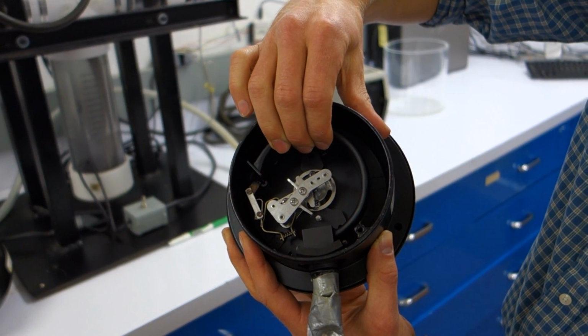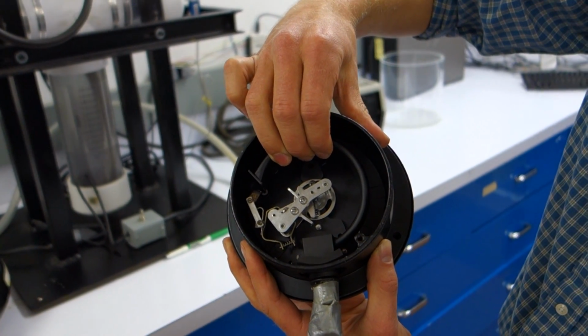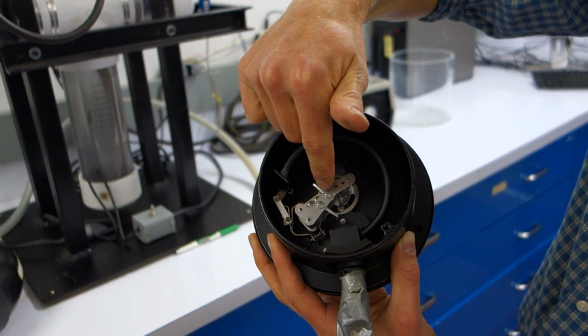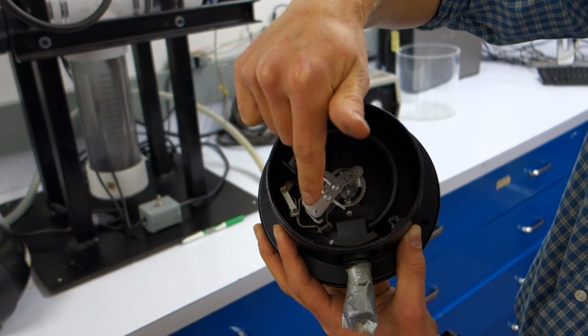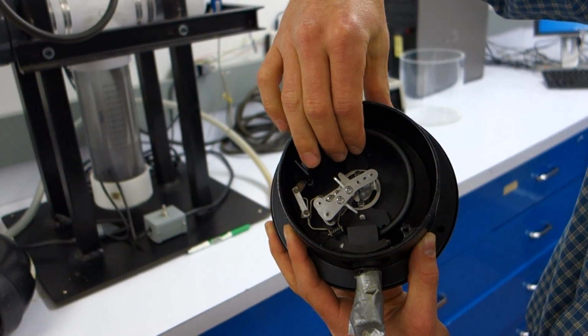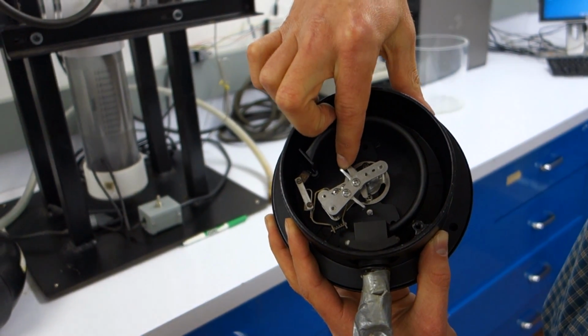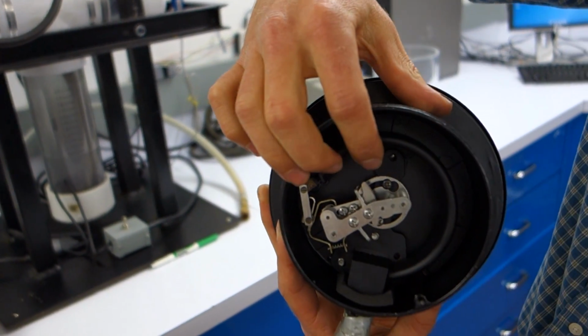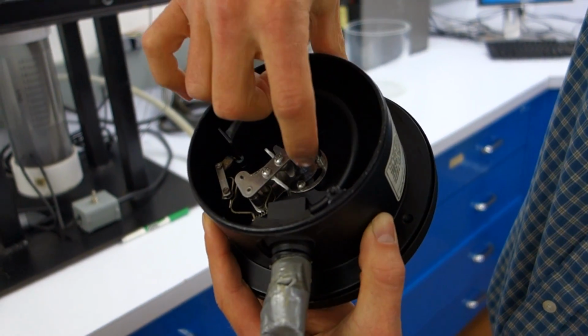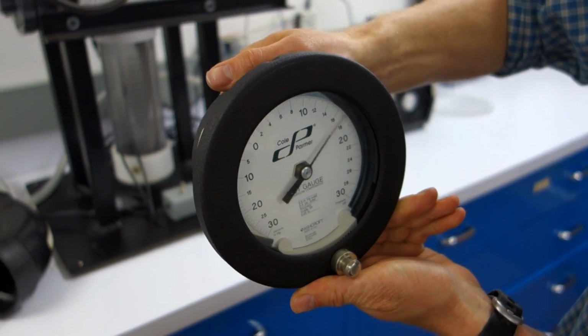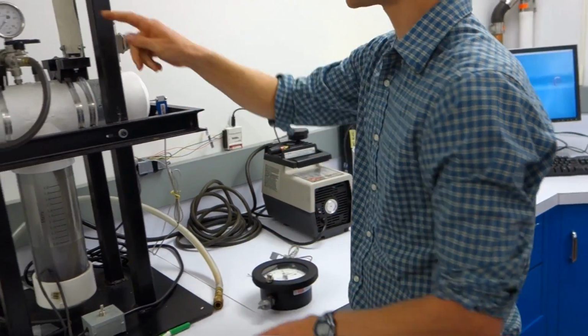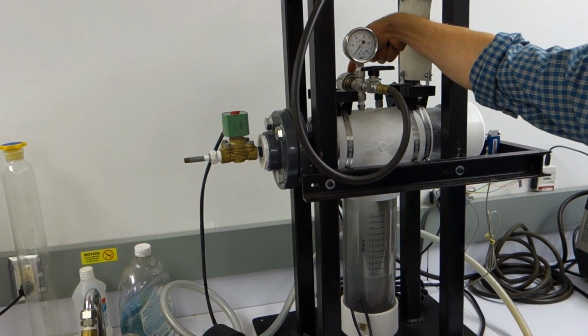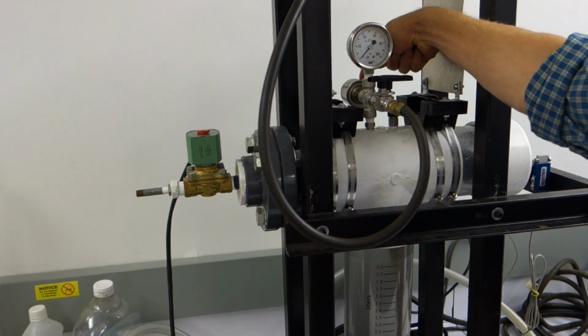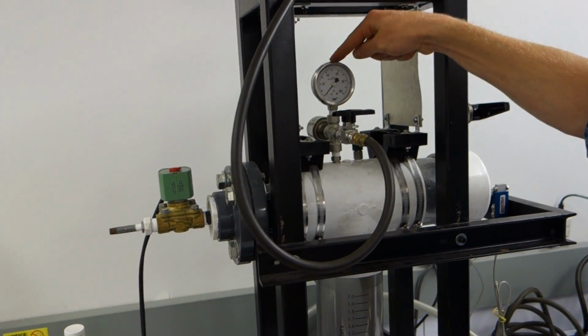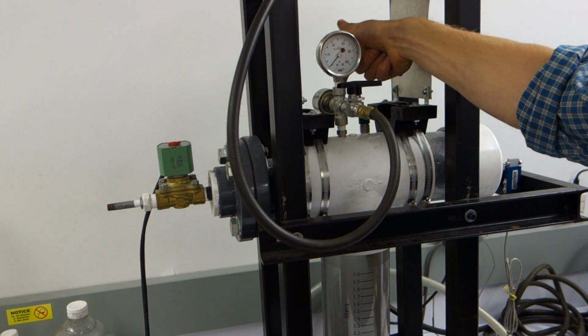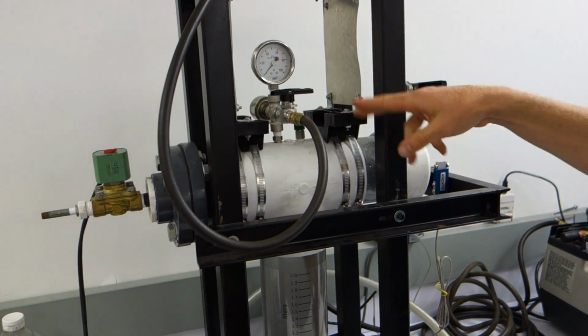So as the pressure increases, the element opens up, and there's a nice mechanical linkage here, tunable with different distances and different spring constants if you want to calibrate it, which is attached to a gear, which is then attached to a small spur gear on this shaft here, which is then attached to the dial. And on the back side of here, there's also an electronic pressure transducer, which I'll talk about the principle behind in a second. So we're reading it visually and on the computer. We're measuring that pressure twice.